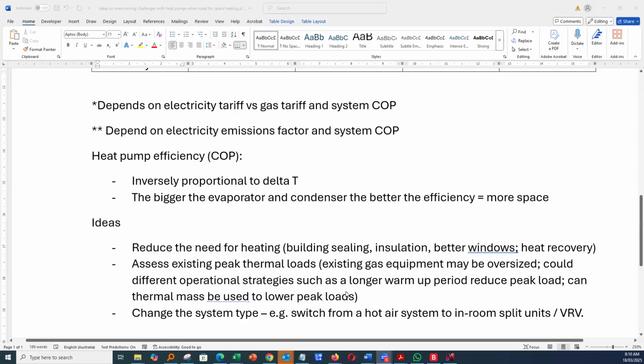Another suggestion would be to change the system type. Now, this is just when there's a major upgrade that happens. So typically, if you've got a boiler-based system, and that system's at the end of its life, maybe you could look to going to a VRV, variable refrigerant volume system, or switch from a boiler-based system with air handling units to maybe a ducted split, or split systems like a VRV system. So that way we can have a lower temperature to deliver the same amount of comfort.